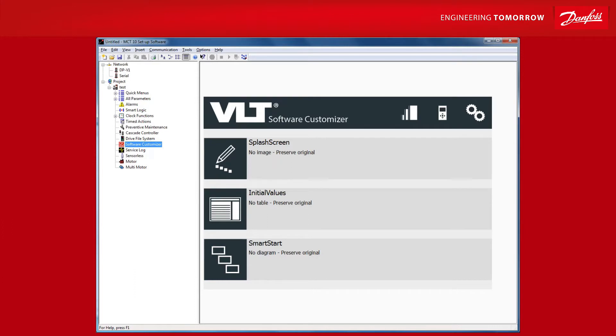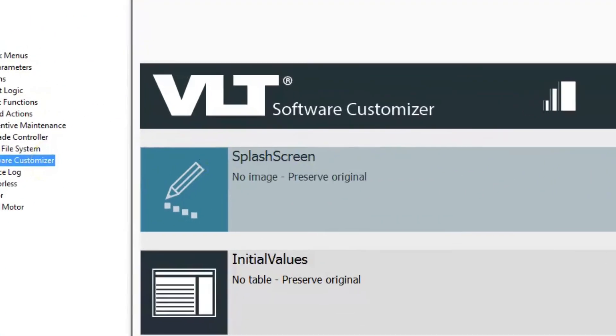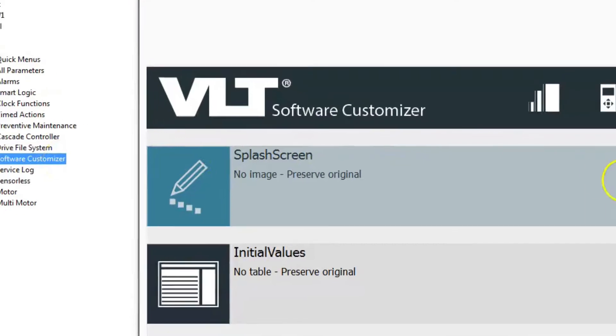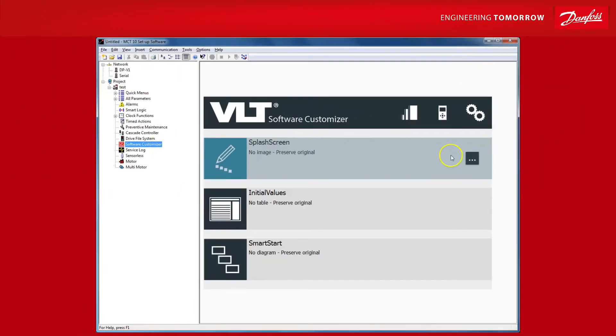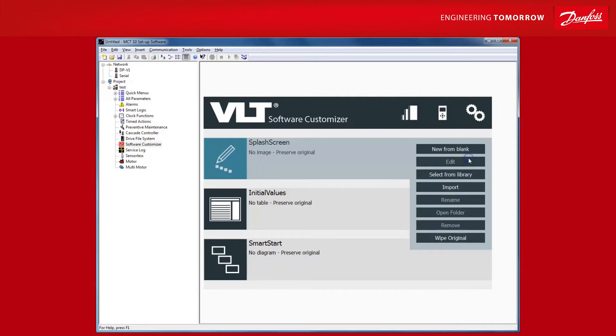Let's start with the splash screen. Here it says what the splash screen will be when you upload your VLT software customizer project to an actual drive. By default, it will preserve the original splash screen that the drive is delivered with from the factory. Click here to see your possibilities. You can create a new image using the built-in editor. You can select from a library of images you've used previously or you can import an image from your computer. This last option removes the default splash screen meaning the drive shows no splash screen when it is powered up.